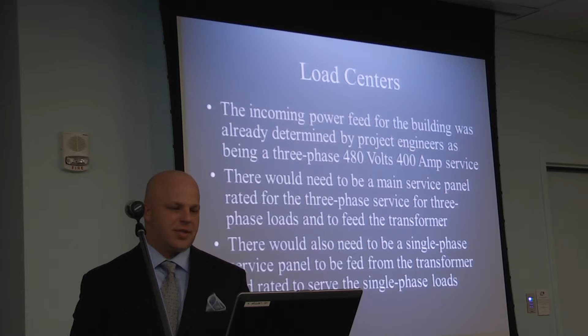For the load centers, the incoming power feed had already been determined by project engineers as being a 3-phase 480 volt, 400 amp service. There would need to be a main service panel rated to handle the 3-phase service for all the 3-phase loads, as well as feed the single-phase transformer. There would also need to be a single-phase service, fed from the transformer and rated to serve the single-phase loads. The load center for the 480 volt 3-phase main was a Square D I-Line panel with a mains rating up to 600 volts and 1200 amps of current. The load center for the 120/240 volt single-phase service was a Square D NQ panel with a mains rating up to 240 volts and 600 amps of current.